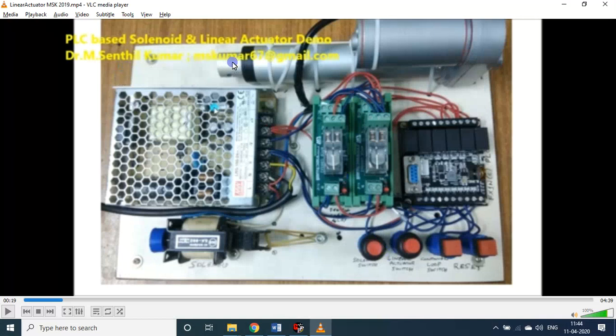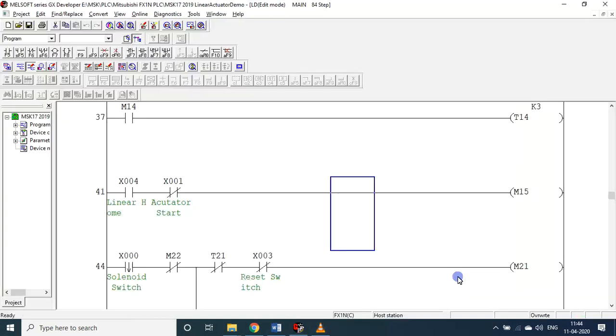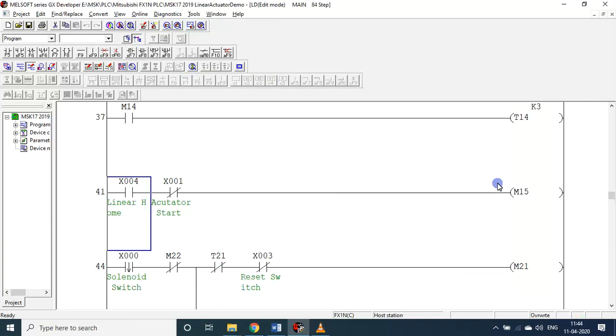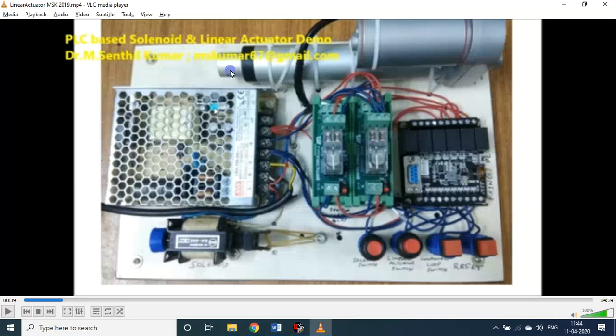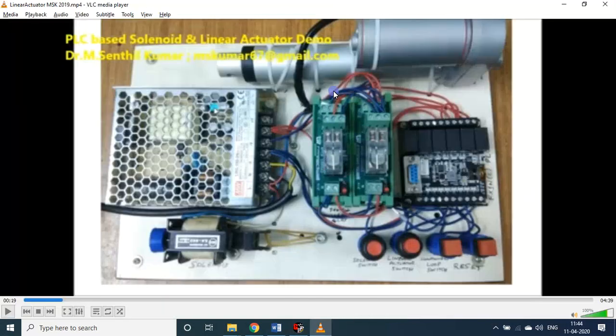This is the zero position. Once you trigger it will move 100 mm, wait for 0.3 seconds and return back. But if there is any power failure in between, the actuator will be somewhere between 0 to 100. It has to be brought to 0th home position. For that only I have given this X4 for the return stroke especially. The return stroke only makes the actuator come to the home position.